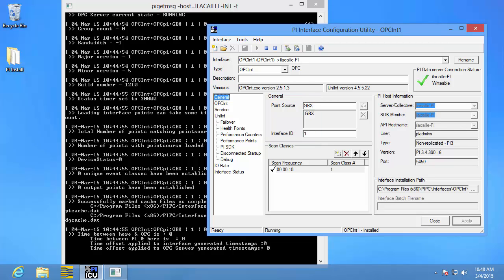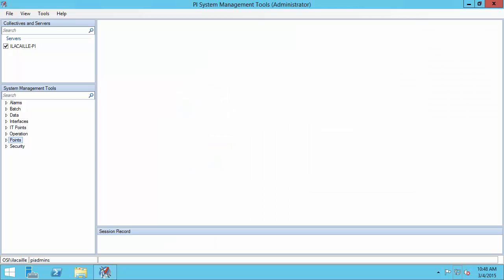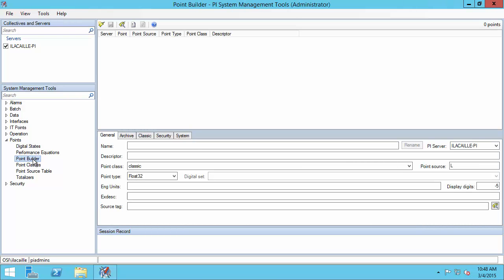Now we're ready to go to PI System Management Tools. We need to go into Points and Point Builder in order to create a new PI point. The first thing to choose is the name. PI System Administrators have a naming convention that they follow when they create PI points — for example, the name of the plant, the name of the unit, and the name of the attribute.